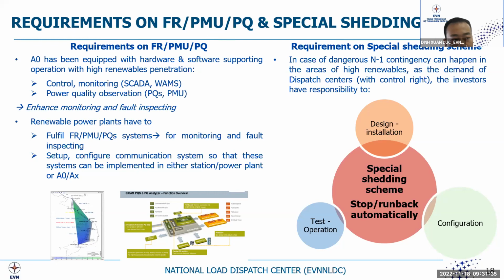Up to now, we actively use the fault recorder and the PMU for monitoring the fault ride-through performance of each individual renewable energy power plant. We also require a certain setting for the FRT, fault ride-through, for each individual power plant, to make sure that when a fault occurs in our system, all the renewable energy has to participate and contribute in terms of megawatts and also in terms of reactive power to the grid.